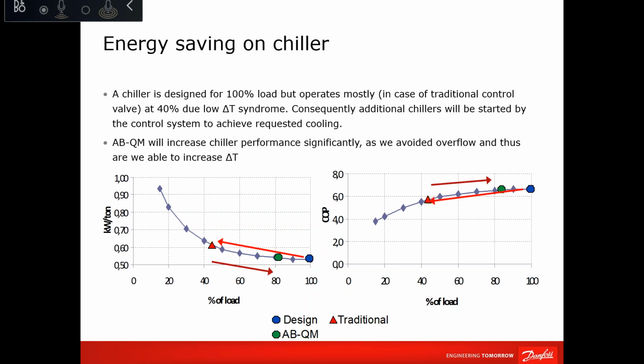Now, because of the overflow in the system, the suction temperature of the refrigerant will drop. And if the suction temperature of the refrigerant drops, the compressor will require more work to heat up from 9 degrees to 40 rather than from 12 degrees to 40. So that is why in district cooling applications recently, they are applying surcharges. Why? Because these surcharges are due to the low delta T from the building.